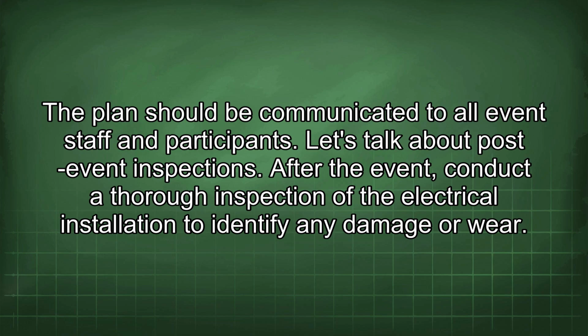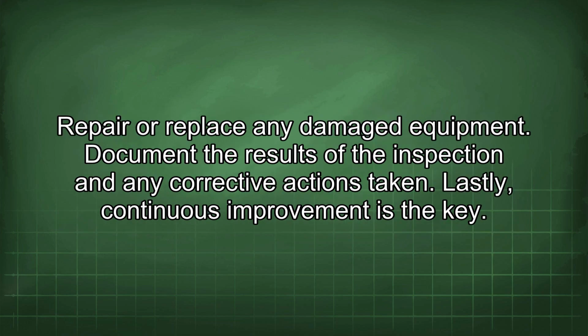Let's talk about post-event inspections. After the event, conduct a thorough inspection of the electrical installation to identify any damage or wear. Repair or replace any damaged equipment. Document the results of the inspection and any corrective actions taken.